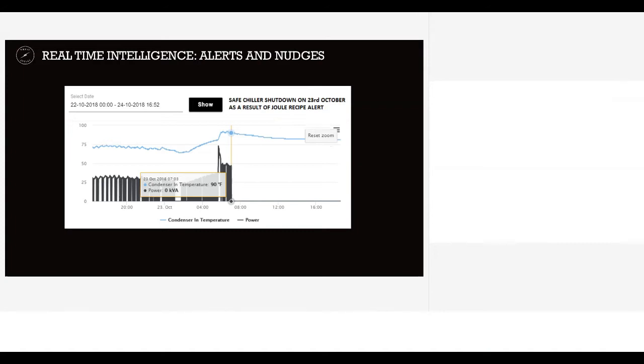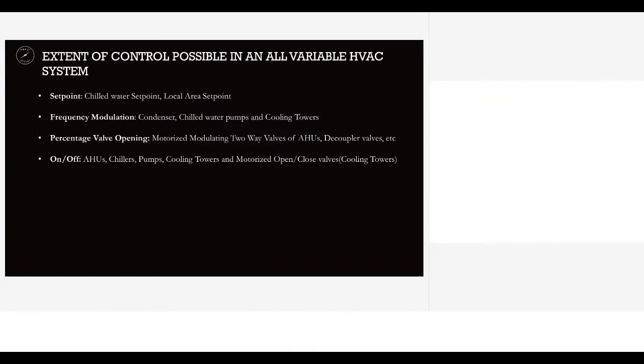This particular scenario happened when we only had monitoring. But what happens next? When the condenser entry temperature crosses 90 degrees Fahrenheit, the safety limit for that parameter, we are able to shut down the equipment through our own IoT platform. We sense that something abnormal is happening and shut down the equipment in safety. So without damaging the equipment, even if the operator handling the plant is not available, we can shut down the plant in safety using data pulled from the system through IoT, protect the machine, and restart once the condition is resolved. These kinds of simple alerts or nudges can be generated.